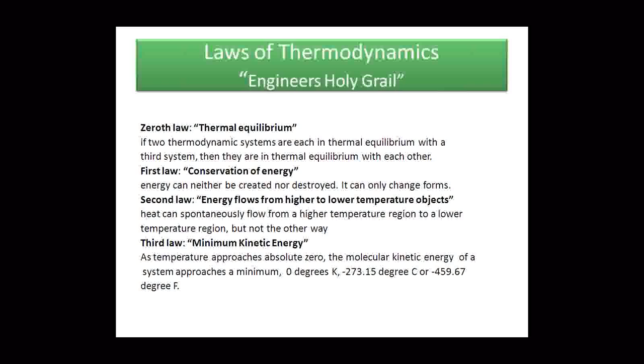Now we capitalize on conservation of energy, because what we're doing is bringing thermal energy back from campus through our chilled water loop, moving it through our refrigerant system and heat pump chiller, inserting that on the discharge side, the hot water loop, and reusing it in buildings that want that thermal energy for heating purposes.